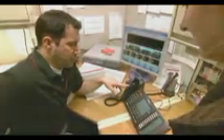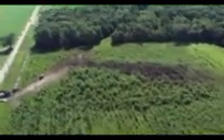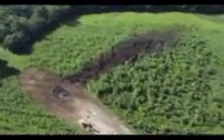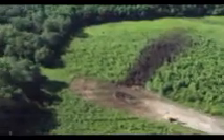The conference call involved other subject matter experts and operations supervisors, and the course of action decided on was to get a pilot up into the air to fly the pipeline and see if he could confirm a release anywhere along the pipeline. And he did indeed find, from what he described, about a 300-foot spray of crude oil over vegetation just upstream of Albion Station. The station went down on low suction.